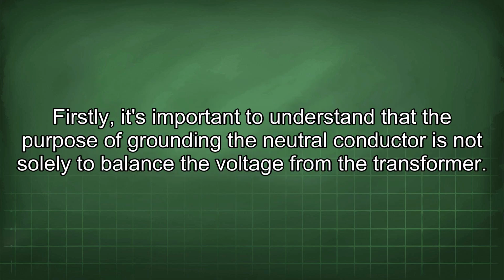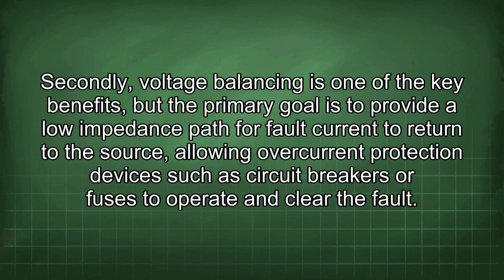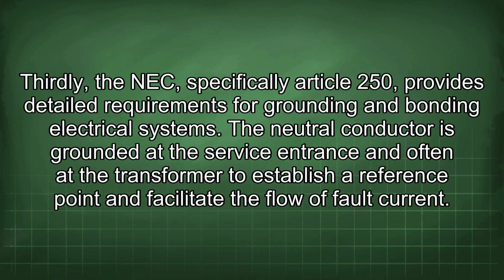Firstly, it's important to understand that the purpose of grounding the neutral conductor is not solely to balance the voltage from the transformer. Secondly, voltage balancing is one of the key benefits, but the primary goal is to provide a low impedance path for fault current to return to the source, allowing overcurrent protection devices such as circuit breakers or fuses to operate and clear the fault. Thirdly, the NEC, specifically Article 250, provides detailed requirements for grounding and bonding electrical systems. The neutral conductor is grounded at the service entrance and often at the transformer to establish a reference point and facilitate the flow of fault current.